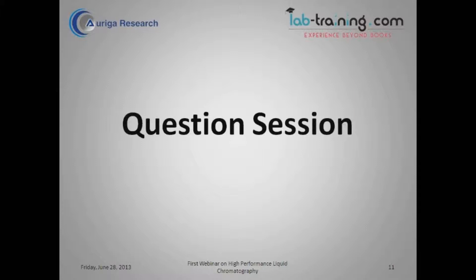Okay, we have got another question coming in that I have seen lot of methods online and in standard books also and I have noticed that mostly they use a UV detector. Why is it so, why is UV most widely used detector? Dr. Deepak? Yes, UV detector has a characteristic that most of the organic compounds have strong absorption bands in the UV region and particularly at 254 nanometers. So this is one wavelength which you will come across in a number of applications. So this is the main reason why most of the HPLC units are using a UV detector.